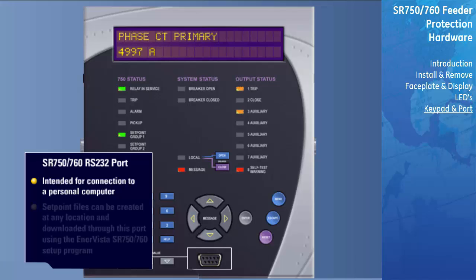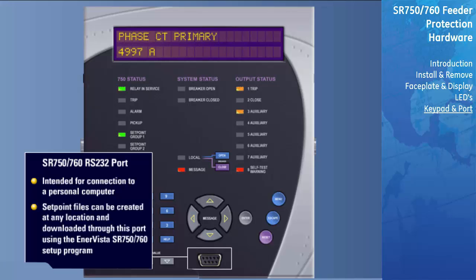The Relay Front RS-232 port. This port is intended for connection to a portable PC. Setpoint files may be created at any location and downloaded through this port using the EnerVista setup program. Local interrogation of setpoints and actual values is also possible. New firmware may be downloaded to the relay flash memory through this port. Upgrading of the relay firmware does not require a hardware EPROM change.